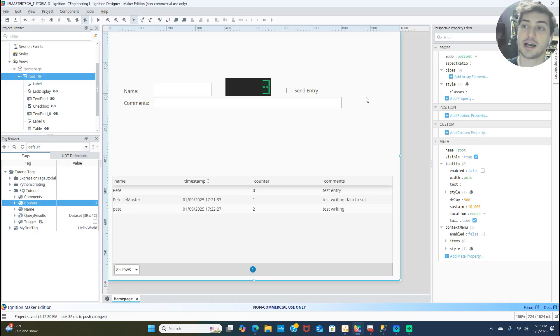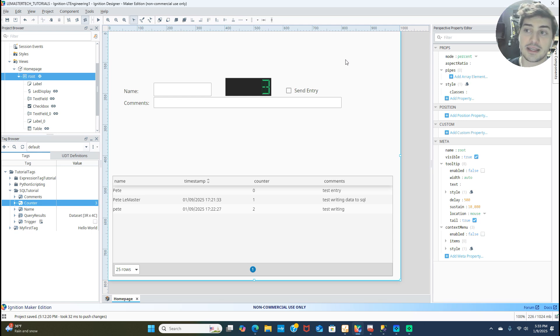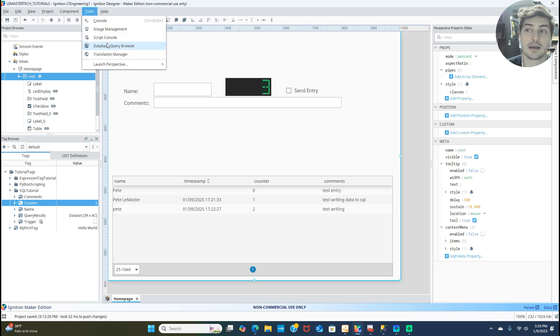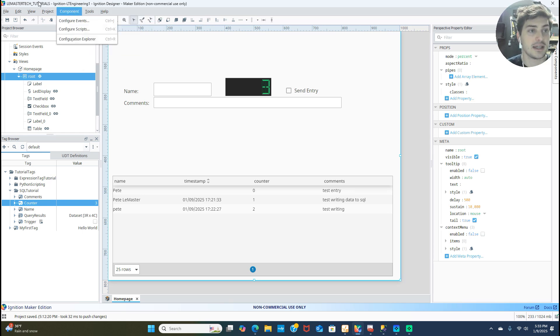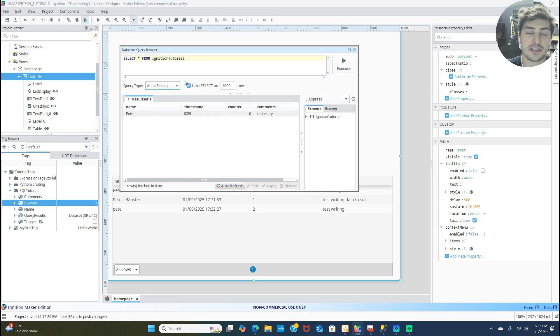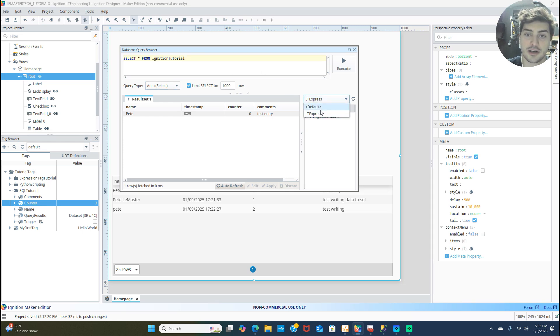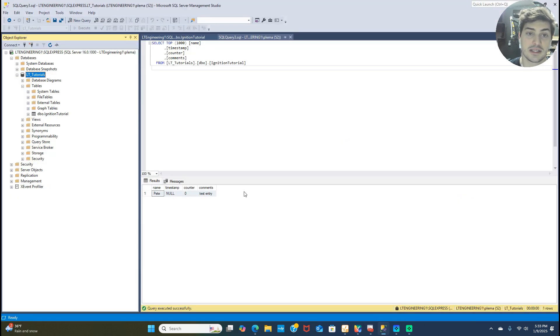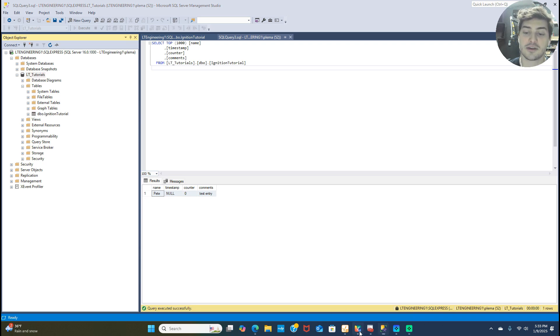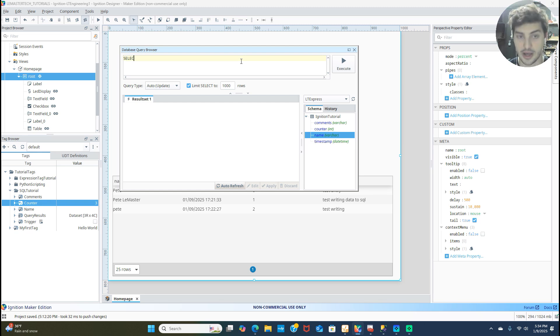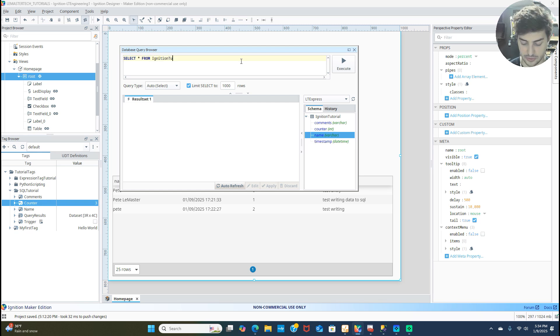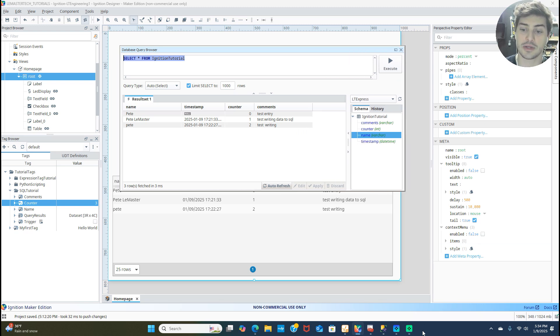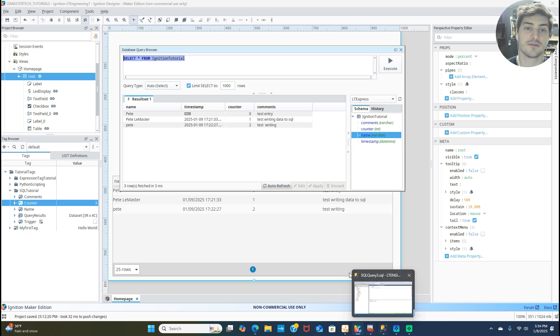So let's look at the Ignition designer. Again, I have a decent walkthrough test already here that I'll show you guys in a second. But the easiest way to verify that you can see and do what you want to see and do in SQL from Ignition is you go to tools in the top bar of the ignition designer, you go to tools and then you go to database query browser. And then you should over here see all of the databases that your gateway is connected to. I have LT Express. But here I can see Ignition tutorial. And if I were to go into SQL and make a second table in that database, I'd be able to see that here as well. This database query browser is actually super useful. You can write in structured query language SQL right here in the browser. So select all from Ignition tutorial. You can do that right here and make sure that your connection is good. So then the data pulls in and you're doing all of this in Ignition. You don't need the management studio or anything else to view this.